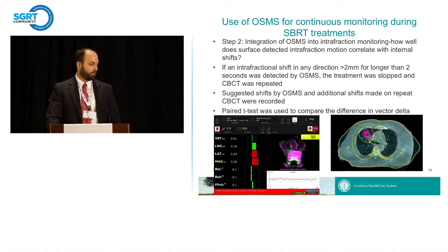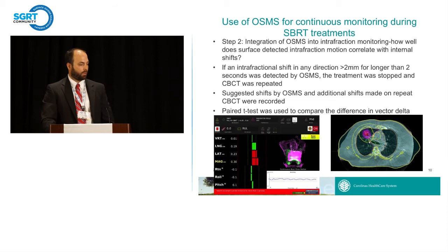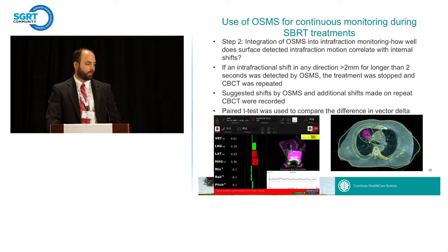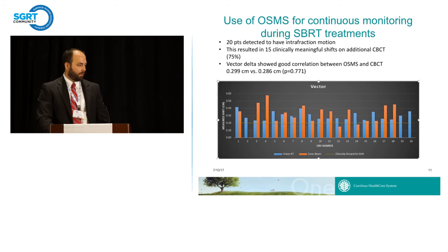Probably the more important reason to integrate OSMS into SBRT was for continuous monitoring, as most of us do for other treatment types. There wasn't much data beyond SRS on how well it correlated with internal shifts during intrafraction monitoring. We set a very low beam hold threshold of two millimeters — intentionally — since our standard PTV margin is five millimeters, but we wanted to see if close monitoring would allow us to consider reducing margins. We also set a time threshold of two seconds because these patients are free breathing with respiratory cycle variability. We recorded suggested shifts by OSMS when patients went out of threshold and compared to shifts on repeat cone beam CT.